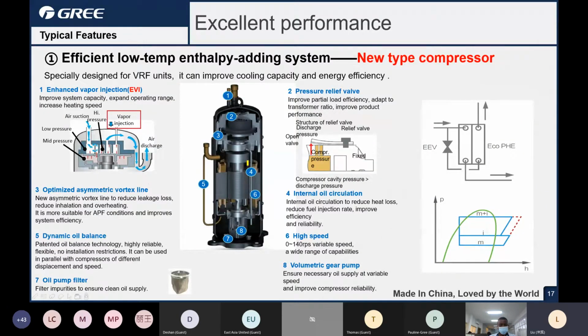Okay, now we look at this slide. In the GMV6 generation VRF, we upgraded the compressor, and now it is the EVI scroll compressor. It has the vapor injection, and now you can see the cross section structure of the EVI. Here is the suction. When the gas refrigerant is sucked into the compressor here and discharged, depending on the operating parameters and environment, the unit will start the vapor injection to improve the performance of the unit.